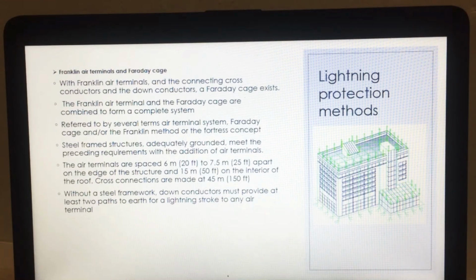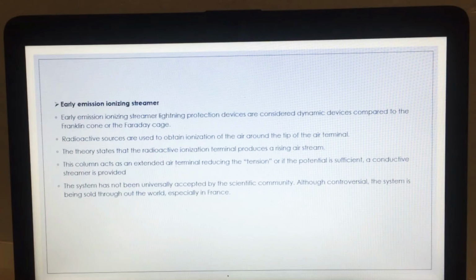The air terminals are spaced 6 meters to 7.5 meters apart on the edge of the structure and 15 meters on the interior of the roof. Cross connections are made at 45 meters. Without a steel framework, down conductors must provide at least 2 paths to earth for a lightning stroke to any air terminal. The second one is early emission ionizing streamer.